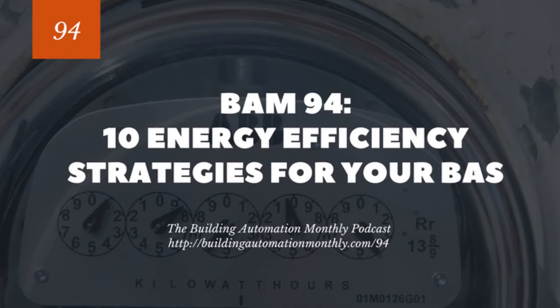So your schedule should, in an ideal world, turn on when people are in the building and turn off when people leave the building. However, there are a couple tips you can take that will allow you to optimize how you schedule your equipment. One tip is to cut the schedule 30 minutes before people actually leave the building. Now, here's what I mean by cut the schedule. I don't mean that you turn off the equipment, but maybe you move the equipment into a lower mode.